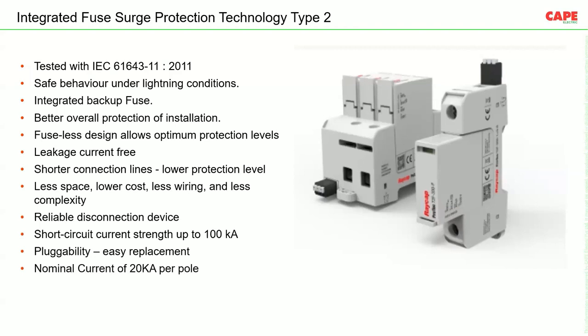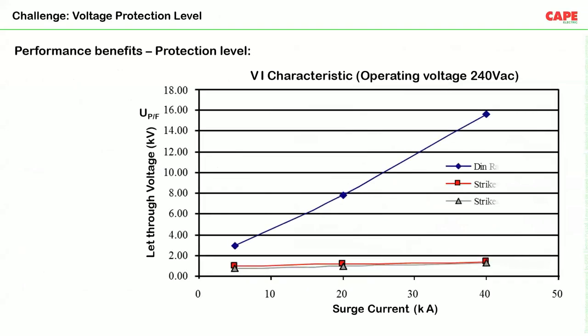These Type 2 SPDs have a nominal current of 20 kA per pole and a response time of 25 nanoseconds. The performance graph shows that even with increasing surge current, the let-through voltage of the SPD remains very low — similar to bus-bar mounted SPDs. SPDs with integrated backup protection have similar performance characteristics, with very low let-through voltage and excellent effective voltage protection levels.